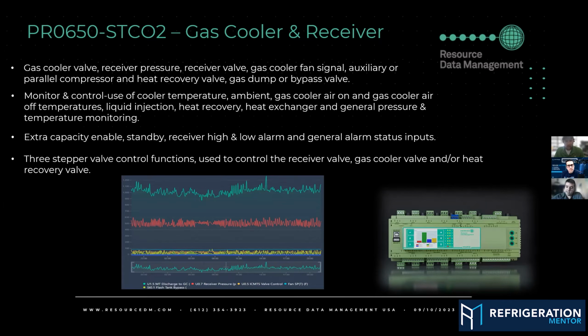So when we're looking at the sites, you're going to see a gas cooler section. That's going to be controlling your gas cooler fans, your high pressure valve, your receiver valve. If you had parallel compression, you're setting that stuff up. Heat recovery, hot gas defrost. That stuff's all kind of optional that you can set up. Got all your usual temp sensors, your cooler inlet, outlet, your ambient. All that stuff can kind of be set up in those sections. And like I said, there's 3 stepper outputs. You can do your high pressure and your flash tank, and you can do heat recovery valve.